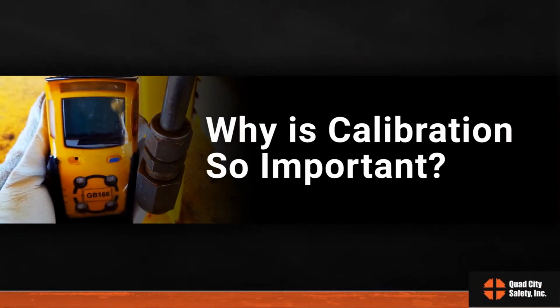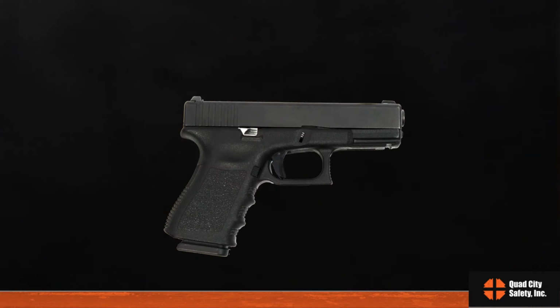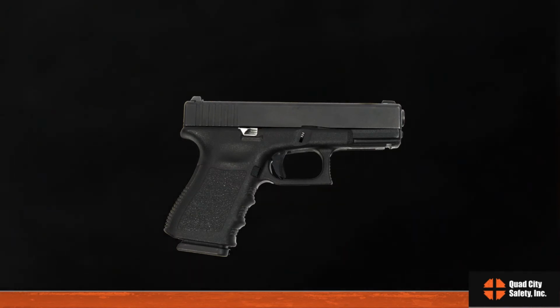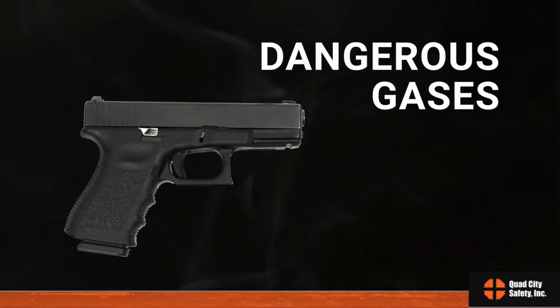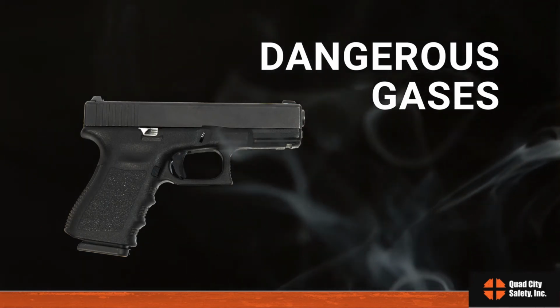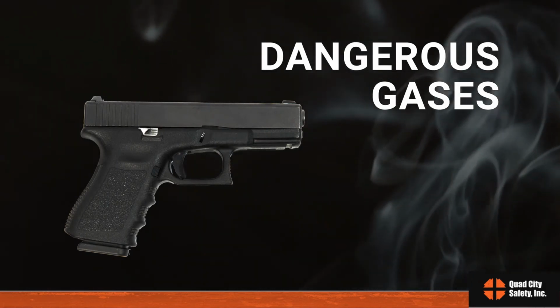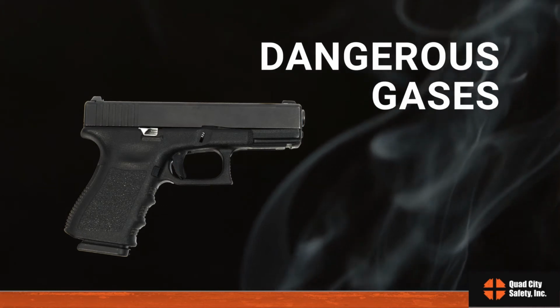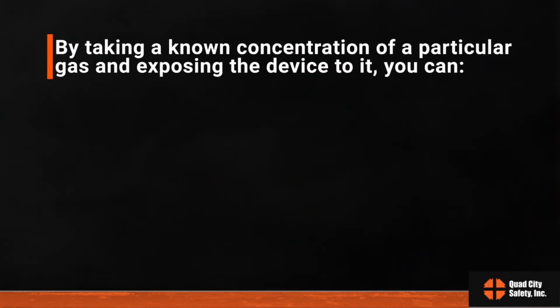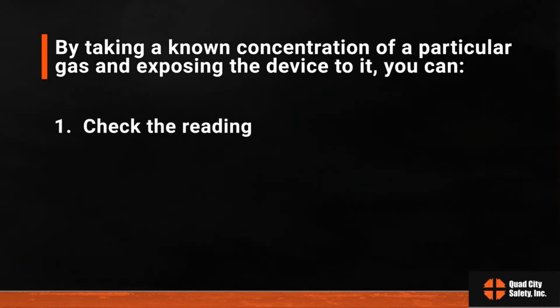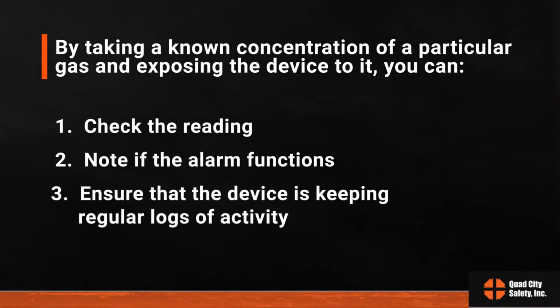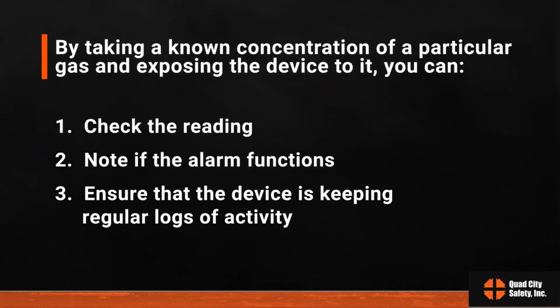So why is calibration so important? You wouldn't mess around with a loaded firearm without understanding how it works, would you? When you're dealing with the potential for dangerous gases, you need to take the same kind of precautions. It can make the difference between workers sustaining life-threatening injuries or going home to their families. By taking a known concentration of a particular gas and exposing the device to it, you can check the reading, note if the alarm functions, and ensure that the device is keeping regular logs of activities.